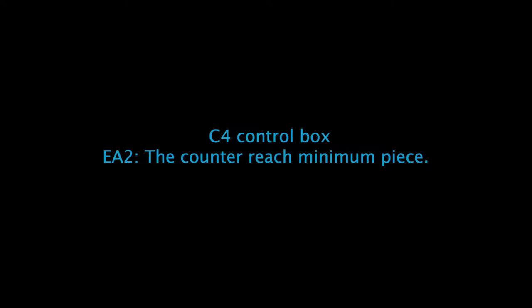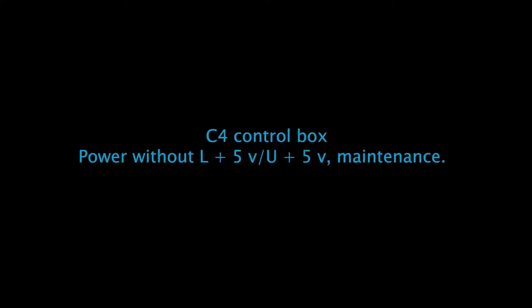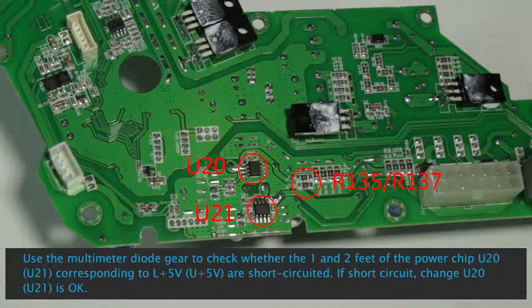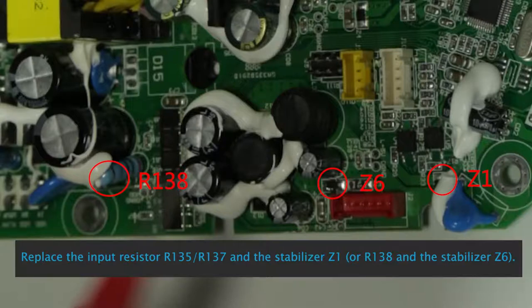C4 control box Ea1 — the counter has reached maximum piece. C4 control box Ea2 — the counter has reached minimum piece. Power without L+5V / U+5V maintenance: Use a multimeter to check whether the 1 and 2 feet of power chips U20 and U21 corresponding to L+5V and U+5V are short circuited. If short circuit, change U20-U21. Replace input resistors R135, R137 and stabilizer Z1, or R138 and stabilizer Z6.